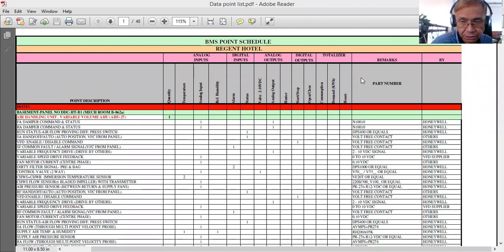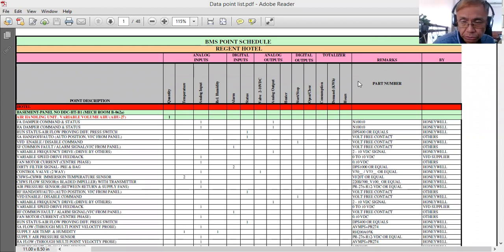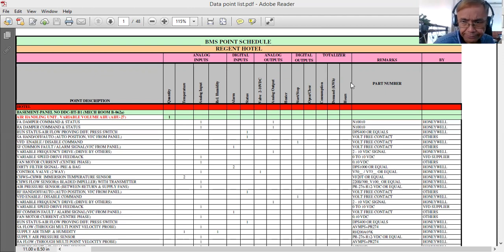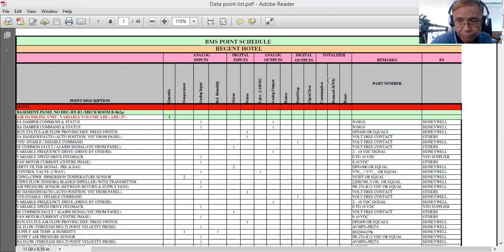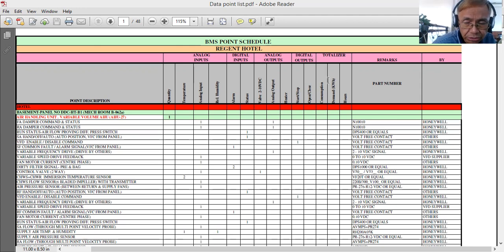Your basis is the project specification. You are very lucky if your project has a predefined data point schedule. What you will do is create your own BMS point schedule. What I have on my screen is an example of a BMS point schedule prepared by a BMS engineer of Honeywell. This project has two BMS engineers — I am the BMS engineer from the MP company. We invited several players in building management systems like Honeywell, Trane, Siemens, Delta Controls, and Alerton to give their offers.